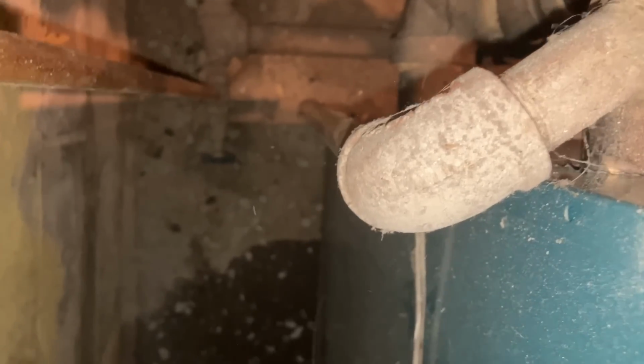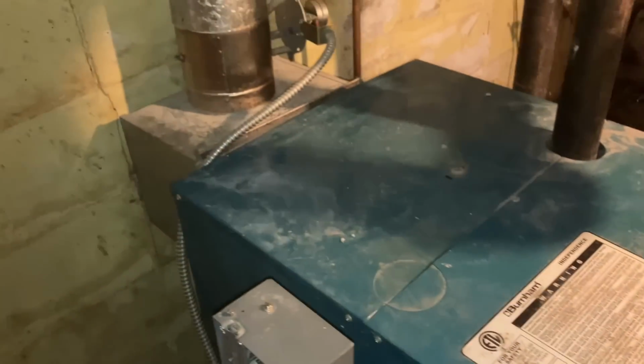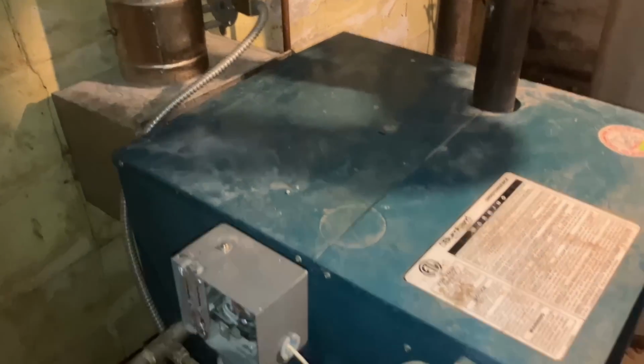Our relief valve, hopefully it's 15 PSI. Yeah, I'm gonna guess that it is. What does that say right there? Yeah, 15. Drip leg. Yep, goes down to the floor. Let's just spray off the top of this boiler and start up our Testo combustion analyzer.